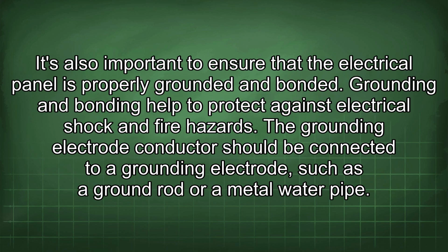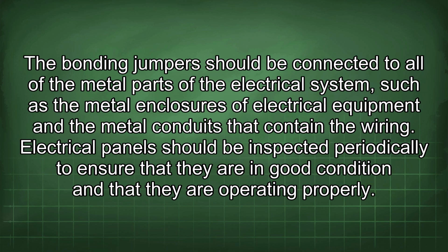It's also important to ensure that the electrical panel is properly grounded and bonded. Grounding and bonding help to protect against electrical shock and fire hazards. The grounding electrode conductor should be connected to a grounding electrode, such as a ground rod or a metal water pipe. The bonding jumpers should be connected to all of the metal parts of the electrical system, such as the metal enclosures of electrical equipment and the metal conduits that contain the wiring.